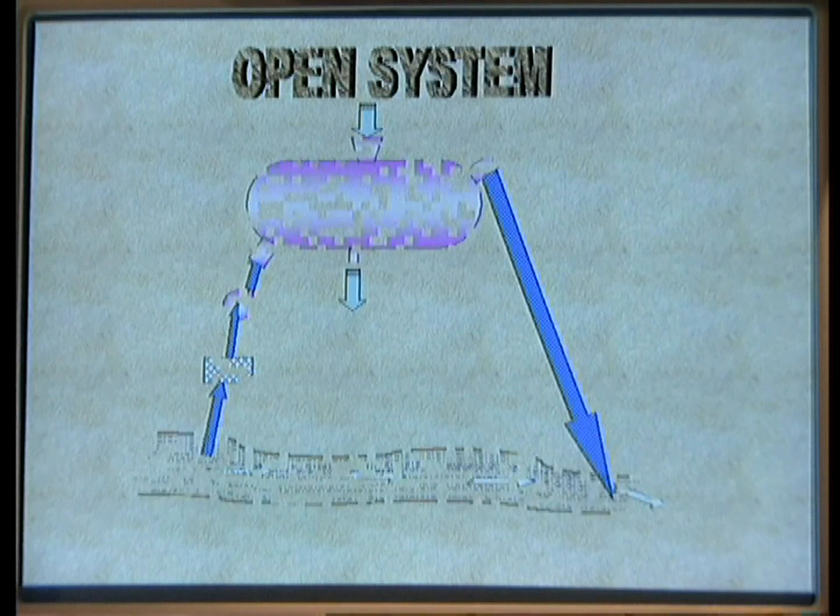So here is a line diagram of the open system. You can see this is a condenser where the water is extracted nearby a river, filtered, and passed through the condenser tubes. Steam to be condensed passes over the pipes, condensate is formed, and it is extracted. The cool water while flowing through the tubes takes the heat from the steam, and next the hot water comes. This hot water is released on the lower side of the river. No need to recirculate or cool it. This is possible when more water is available.